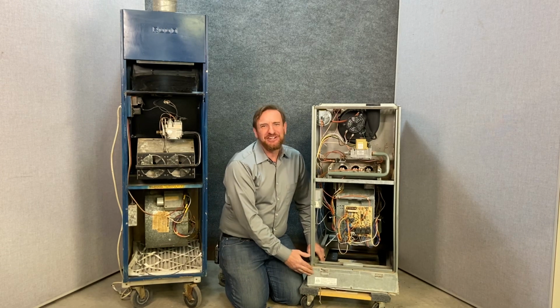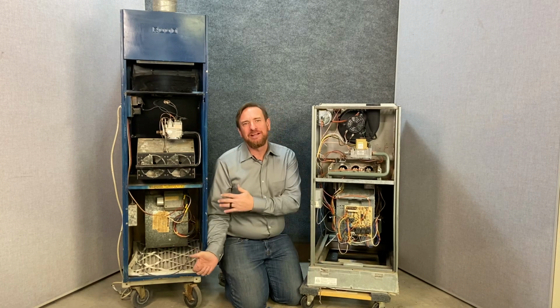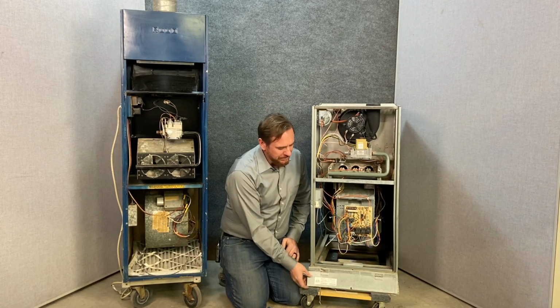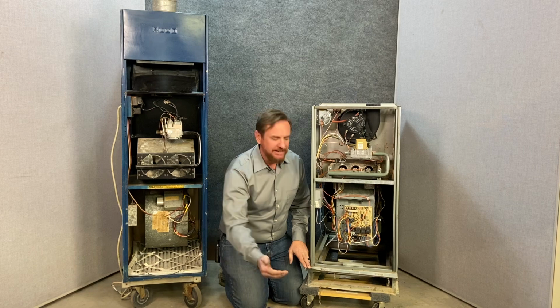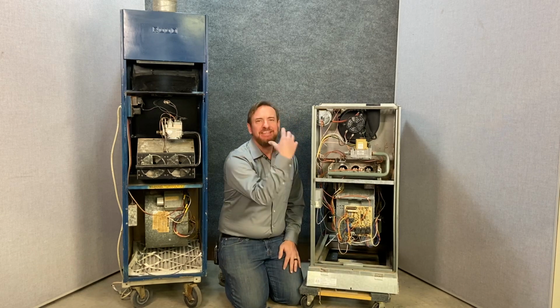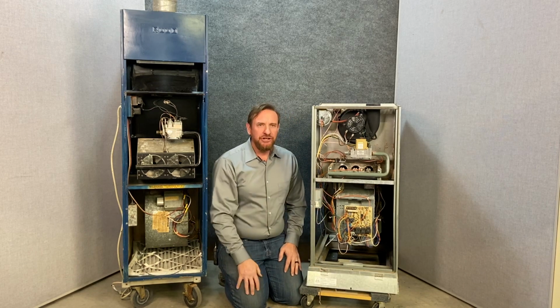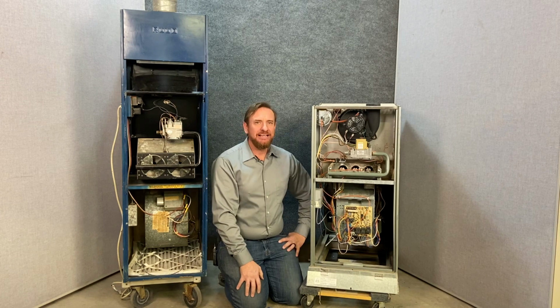It's going to be so much harder to get them to change filters if they have to worry about going through a whole lot of hassle. So this way they can lift this door up, slide the filter out, slide a new filter in, and they're not messing with anything in the system. And remember, a good filter is going to be the key to that system lasting a long time.